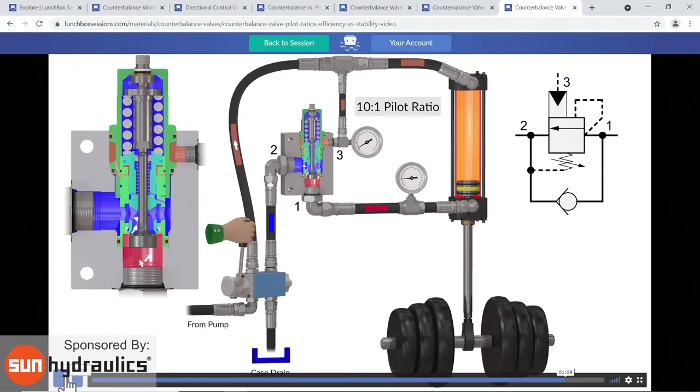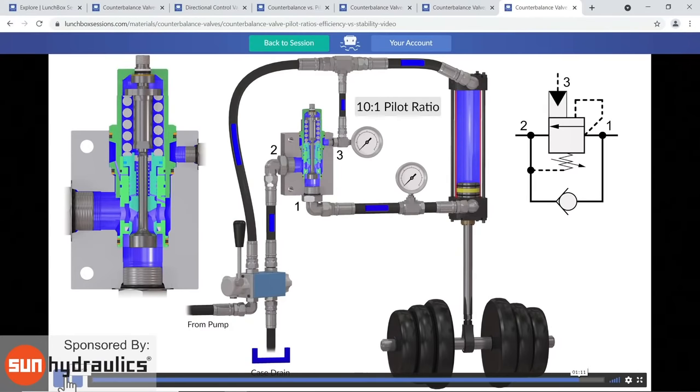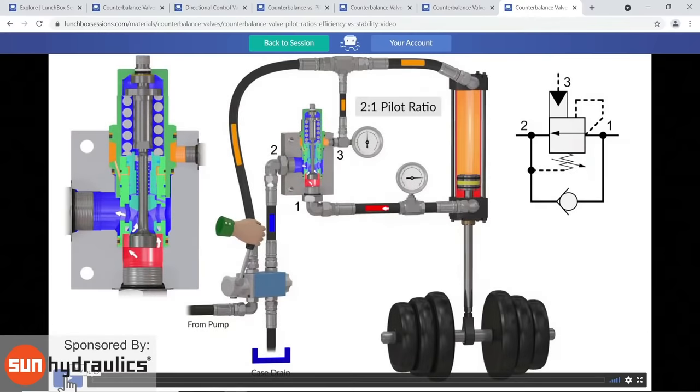And what we noticed is that it took a while before the valve smoothed out. The initial drop created a scenario with a pressure drop so great that the piston moved away from the poppet excessively, and we had some uneven motion, some instability, as it's called.